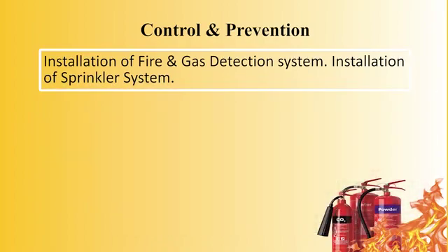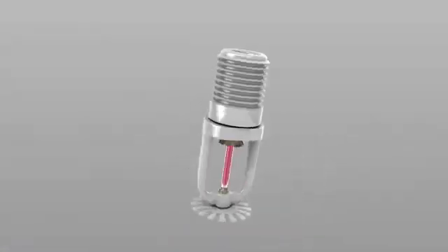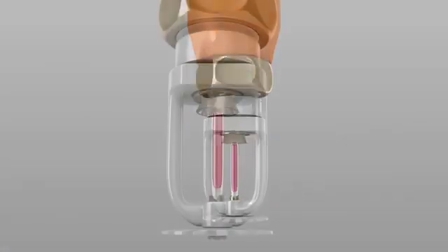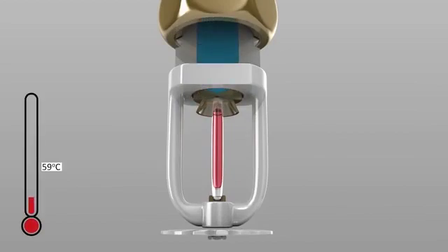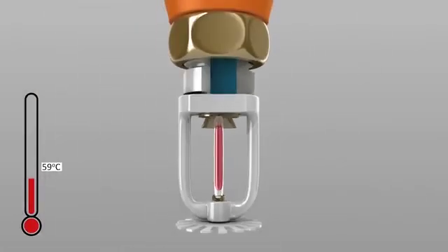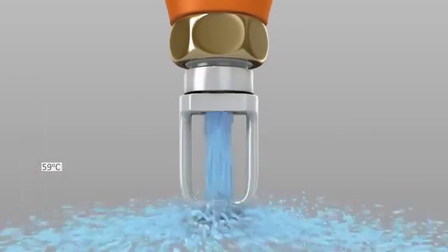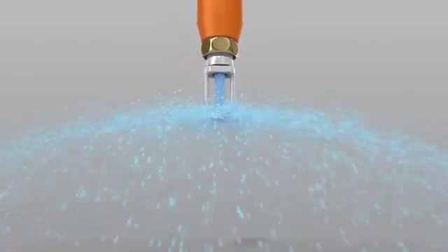And whenever fire occurs, the installed sprinkler will operate. You see, the sprinkler itself is a detector. A quartzoid bulb is there, which indicates a temperature of 59 degrees centigrade minimum; 68 and 79 are also there.